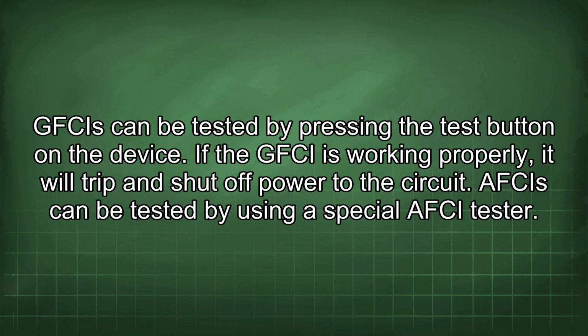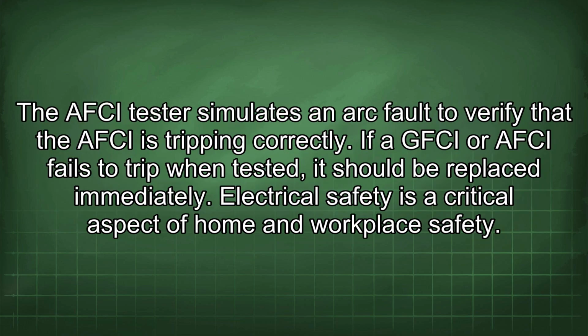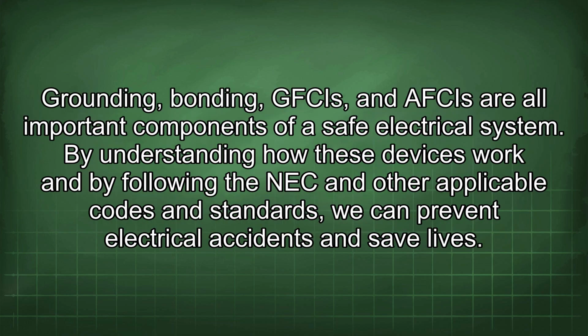AFCIs can be tested by using a special AFCI tester. The AFCI tester simulates an arc fault to verify that the AFCI is tripping correctly. If a GFCI or AFCI fails to trip when tested, it should be replaced immediately. Electrical safety is a critical aspect of home and workplace safety. Grounding, bonding, GFCIs, and AFCIs are all important components of a safe electrical system. By understanding how these devices work and by following the NEC and other applicable codes and standards, we can prevent electrical accidents and save lives.